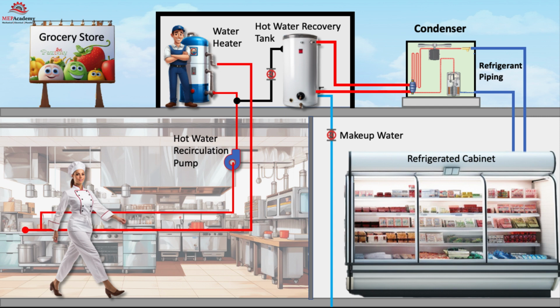3. Heat transfer. The superheated refrigerant passes through the heat exchanger, where it transfers its heat to the water flowing through the heat exchanger. This heat transfer process raises the temperature of the water. 4. Temperature control. The control valve regulates the flow of superheated refrigerant to the recovery tank heat exchanger, adjusting the amount of heat transferred based on the desired water temperature. This ensures that the water doesn't get excessively heated.